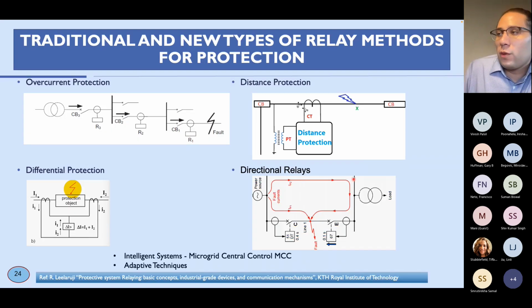We do have traditional and different relay types of methods nowadays. The overcurrent protection, shown on the top left, as I showed before, uses circuit breakers, relays, and fuses. That's the traditional approach implemented at distribution level. We can see there is a fault downstream on the line, and if we don't detect it here, we can detect it in the second section, and we can go up to different curves of faults that they are studying in protection.